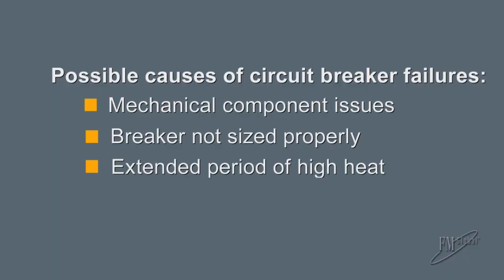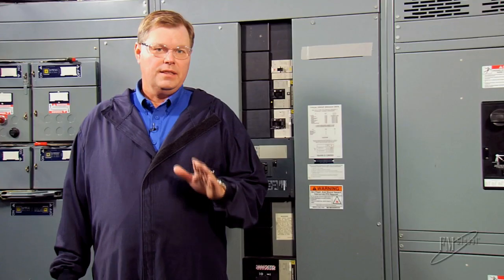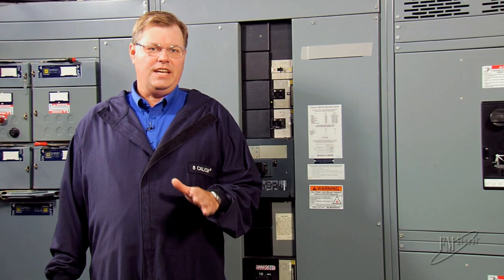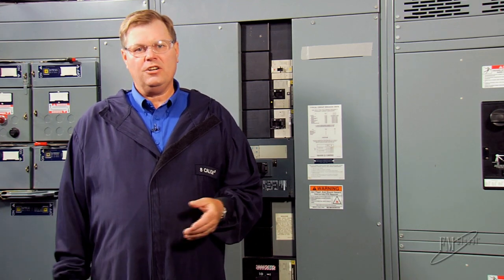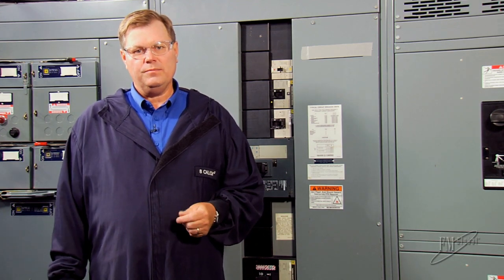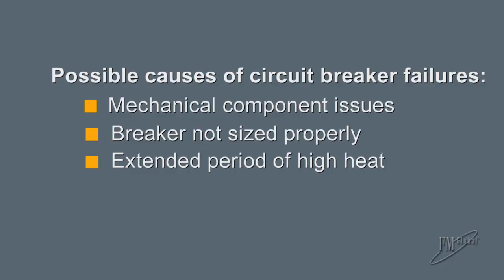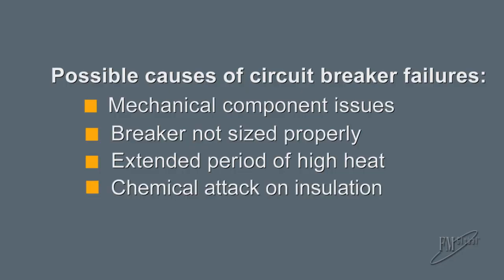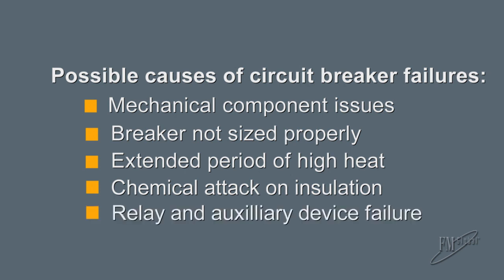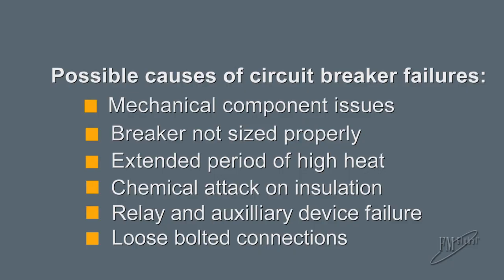In addition, overloading can also occur where the normal load is high enough to cause heating over an extended period. This results in damage to the insulation and mechanical components. Other causes include chemical attack on insulation, relay and auxiliary device failure, and loose bolted connections.